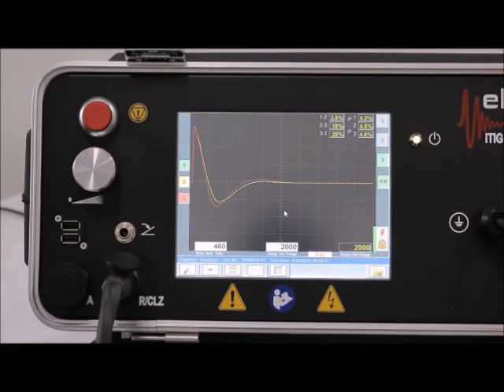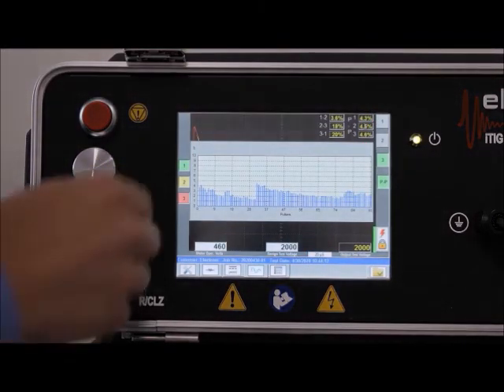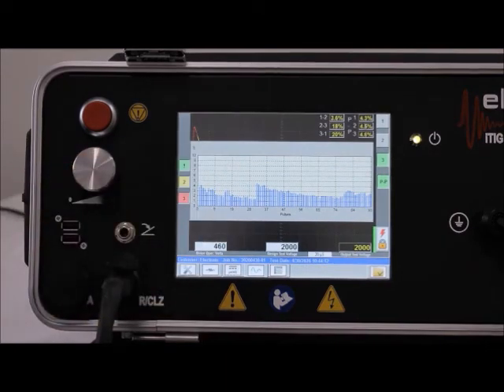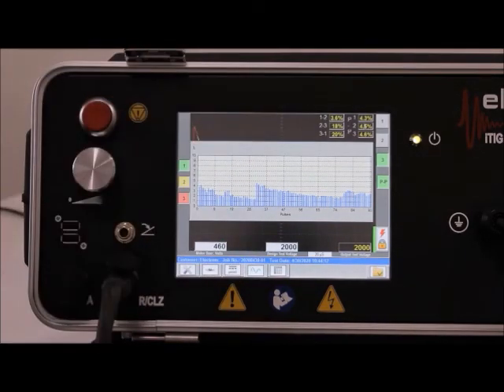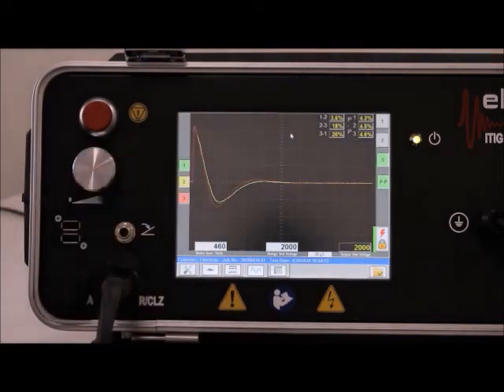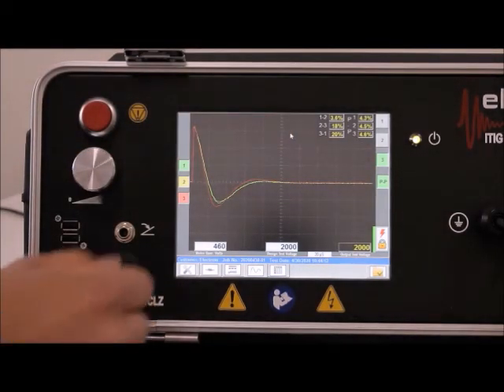Okay, so we have our pulse-to-pulse measurements done. The column on the right-hand side shows the greatest percent wave difference between the voltage step in each individual phase. We also get our line-to-line comparison. We have very nice and low numbers for the pulse-to-pulse. Here, each blue bar represents the percent wave difference between the current voltage step and the previous voltage step. If we detected an arc or a failure of some sort, it would be a very tall blue bar somewhere in this bar chart. Since nothing arced here, we are all good. We have nice low percentages.